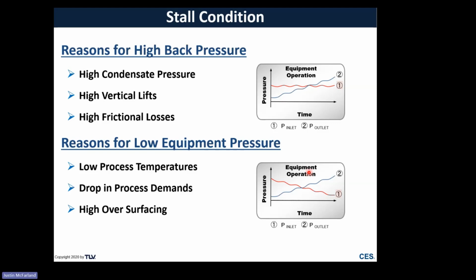Got high oversurfacing. This is an interesting one to think about. If I am a heat exchanger manufacturer, I'm going to recognize that, okay, over time, that piece of equipment is going to degrade. Over time, there's going to be corrosion. There's going to be fouling. I know that if I deliver my piece of equipment today to meet 100% of the BTU requirement, that a week from now, as things degrade, well, it's not going to be able to perform adequately.